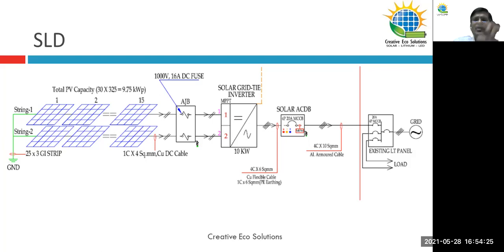Inside the inverter, we will have an MC4 connector slot. So we have to fix it to the male socket and female socket, plus minus plus minus. During the termination, before the MC4 gets connected to your inverter, check the DC voltage with a multimeter before inserting it. Sometimes what happens, we forget which is plus and which is minus, or we mix it up. So always check with the multimeter before terminating it. That will be much better in terms of safety, and it will also prevent inverter failures and lower the risk of short circuit.